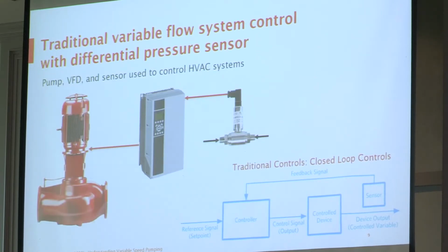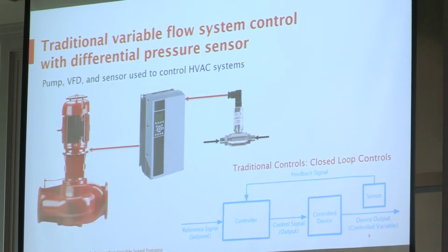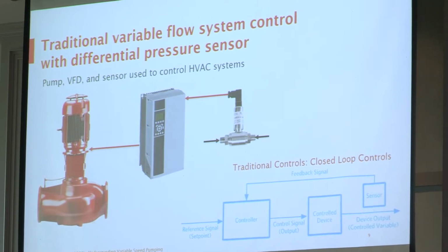So if we look at our traditional systems today, we basically have a pump, a drive, and a differential pressure sensor. So it's a PID loop technology. Basically, you have that DP sensor, which is a diaphragm with 2 ports on either side. And when a valve closes, the pressure changes from one side to the other, you deviate from your set point. When you deviate from your set point, that DP sensor sends a signal back to your drive to either speed the pump up or slow it down. Drive, pump don't know anything other than to get back to their set point. And once they get back to that set point, you're back to your steady state. You're now at your new flow demand.